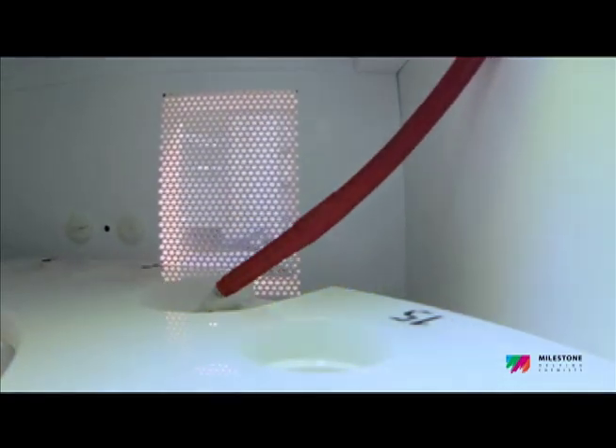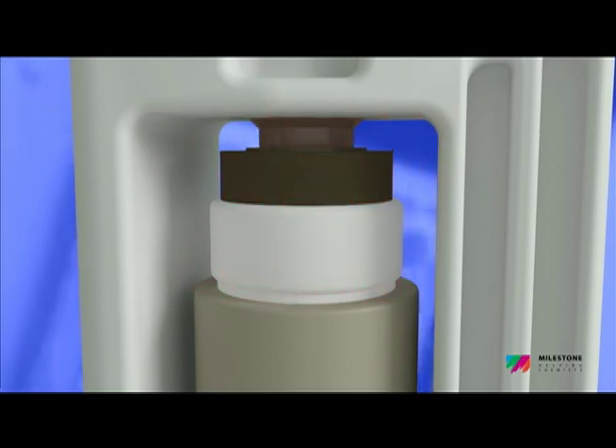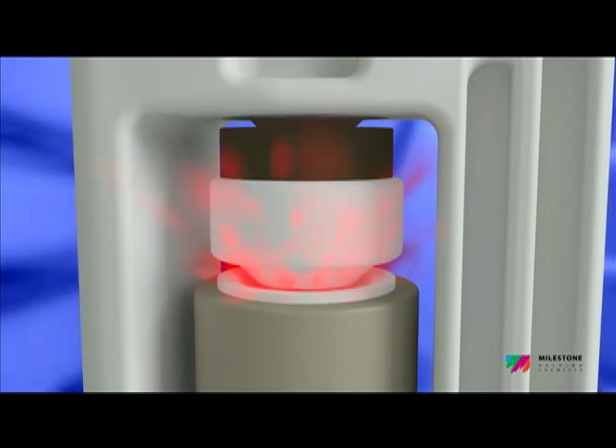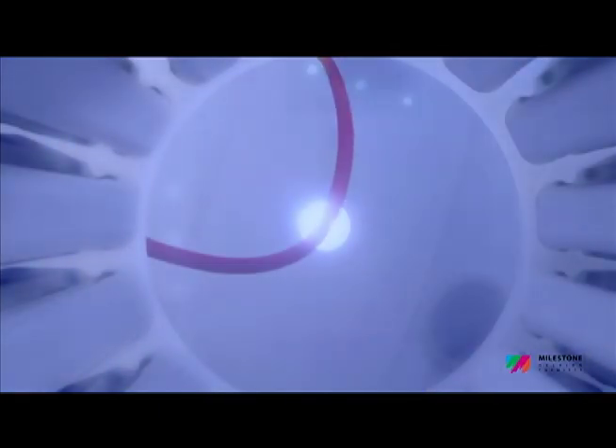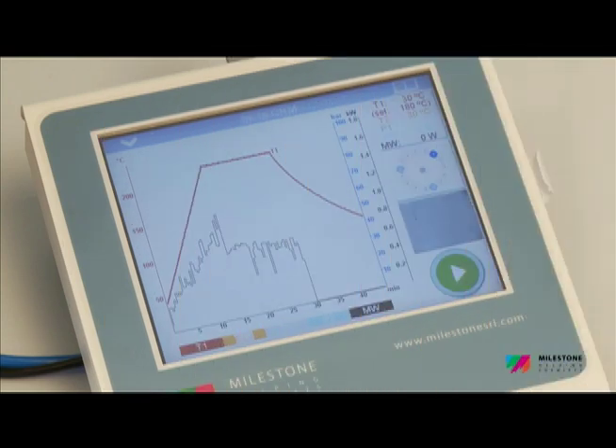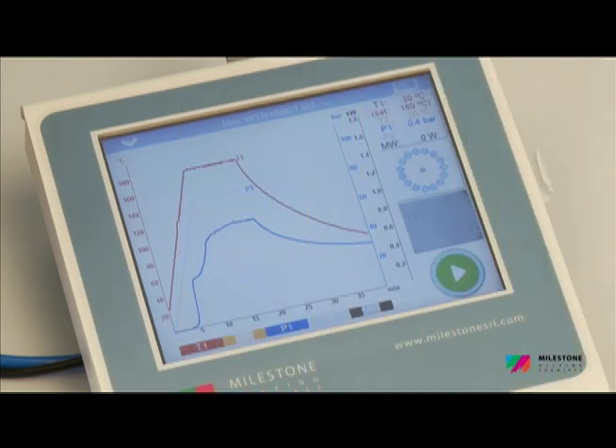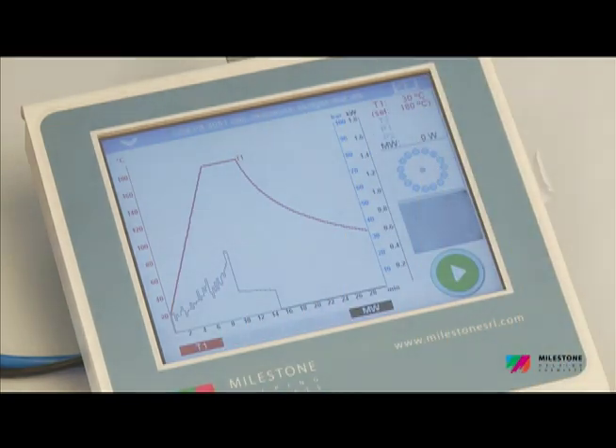The SK15 and the Maxi 44 feature an enhanced vent-and-reseal technology for controlling the inner pressure of all vessels in full safety. The vent-and-reseal approach for pressure release is the foundation of Milestone's leadership in microwave digestion technology. This patented technology provides the operator with unsurpassed safety and performance capabilities, including the highest temperature, pressure, and safety standards.